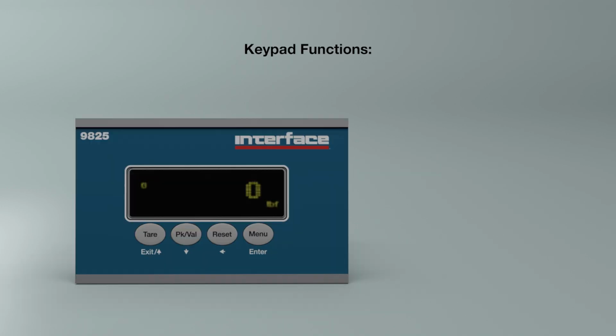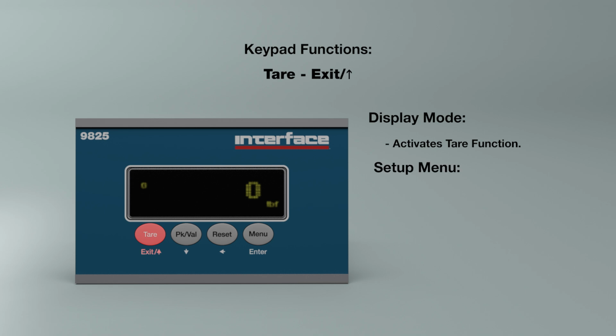The instrument panel. The 9825 indicator has 4 keys on the front panel. Each key functions differently when activated in the setup menu or display mode. Key functions for display mode and the setup menu are outlined below. Tare, exit, and up arrow functions. Display mode will activate tare function. Setup menu will move up through menu structure. Increase digit. Hold down to exit setup menu.